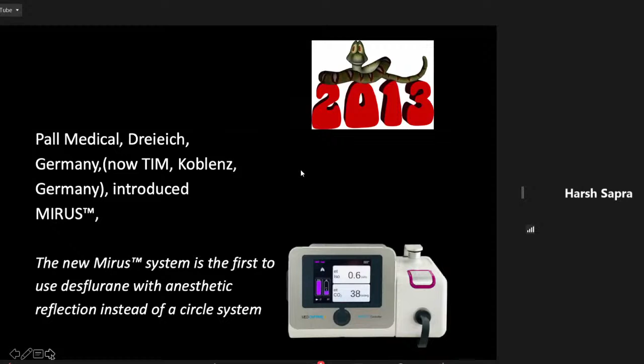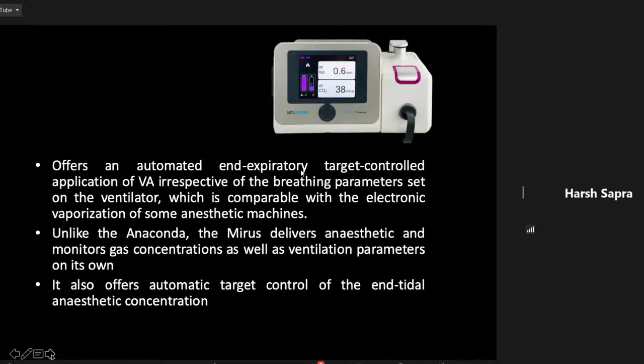in Germany. So it offers an automated end expiratory target controlled application of volatile anesthetic irrespective of breathing parameters set on the ventilators. Unlike the Anaconda, the Mirus delivers anesthetic and monitors gas concentration as well as the ventilator parameters on its own. It also offers target controlled end tidal anesthetic concentration, as you would see with the vaporizers in the theater machines. So it has something similar, a Mac Pilot, which is a special feature of Mirus, a control unit which has monitors and controls the gas flow, pressure, volatile concentrations, and application.